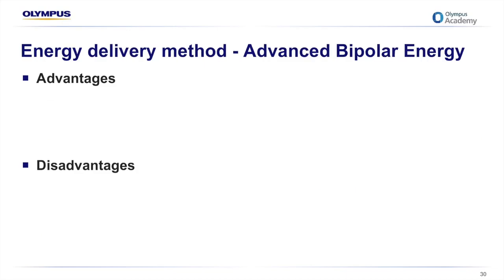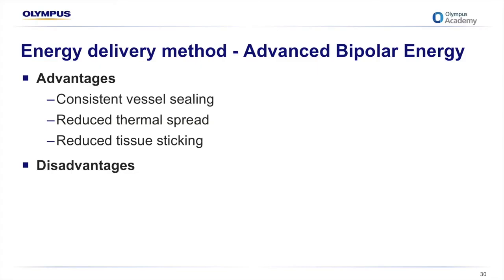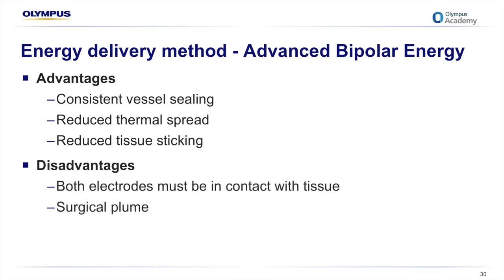The advantage of advanced bipolar energy is that it's measuring impedance. In doing so, you're able to get a reliable, consistent vessel seal, you reduce your thermal spread, and you also reduce your tissue sticking because you're not over-coagulating. However, it's also a bipolar device, so both the electrodes must be in contact with the tissue, which can be challenging, and once again, surgical plume is also created.